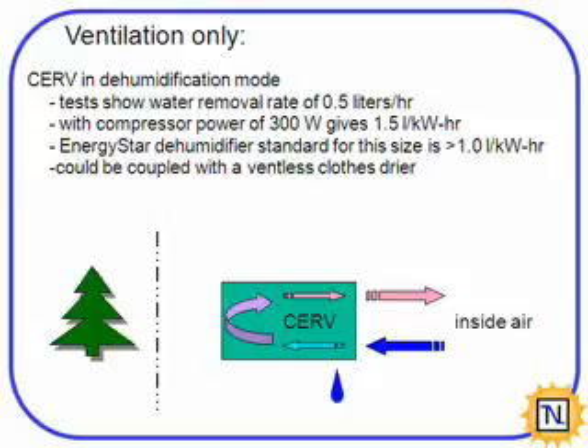The tests we've run have shown 0.5 liters per hour dropped out. Compressor power was 300 watts, so we had 1.5 liters of water per kilowatt hour produced. Standard or Energy Star ratings for this standard size dehumidifier, which you might buy for your own home, need to be greater than 1 liter per kilowatt hour. So with this system, we're already quite a bit above that.